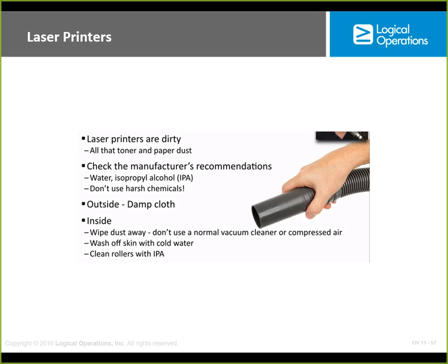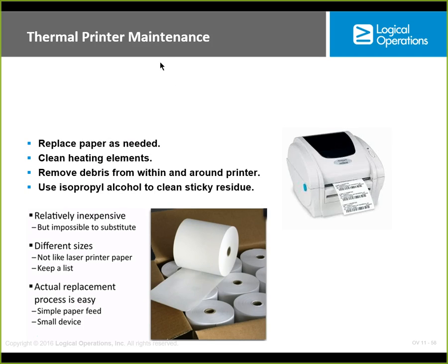Check the manufacturer's recommendations, water or isopropyl alcohol, to clean these things with. For the exterior they usually recommend just a damp cloth. Outside, there it is, a damp cloth. Inside, wipe the dust away. Don't use a normal vacuum cleaner or compressed air. You just blow it all over the place. Wash the skin with cold water and clean the rollers with isopropyl alcohol when you need to do those.